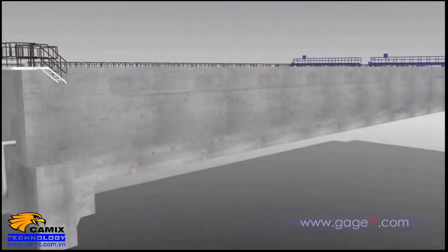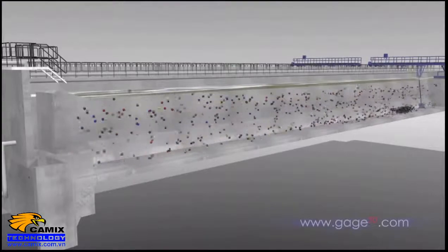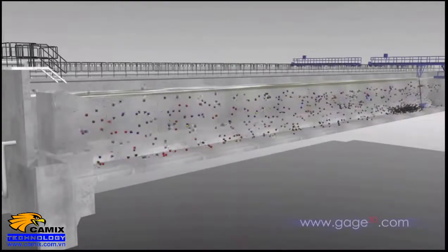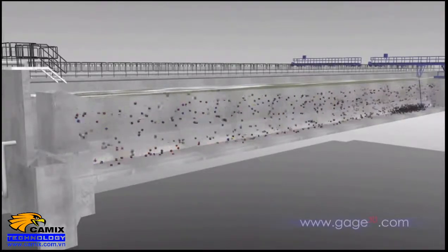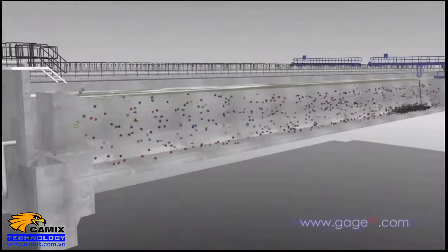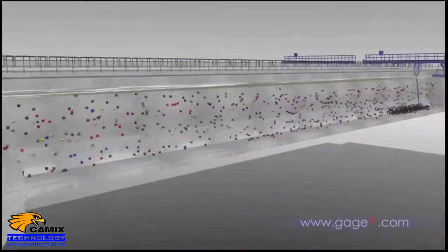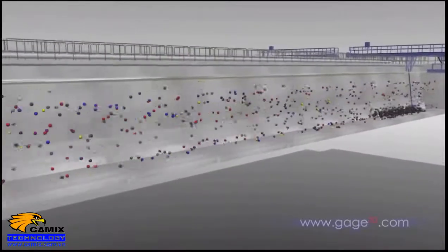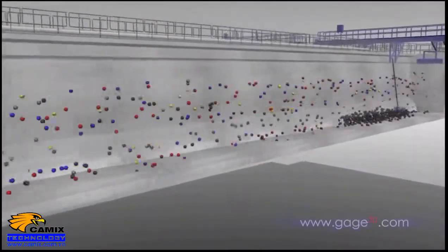The next stop within the headworks is the grit removal chamber. Grit is made up of large, heavy particles like sand or eroded cement. Water flows slowly through this tank, keeping organic matter like food, waste, bacteria or excrement in suspension but giving the heavier grit a chance to fall to the bottom.